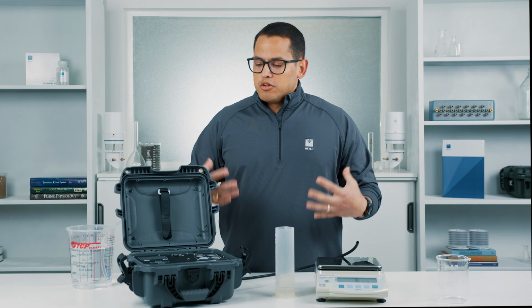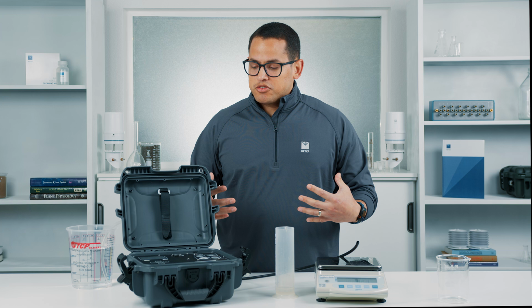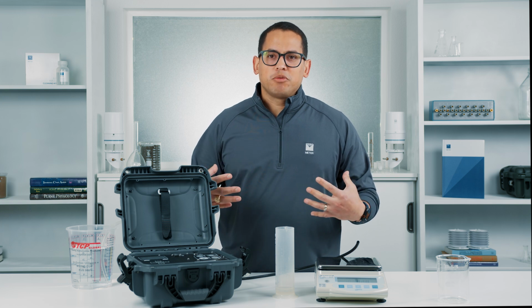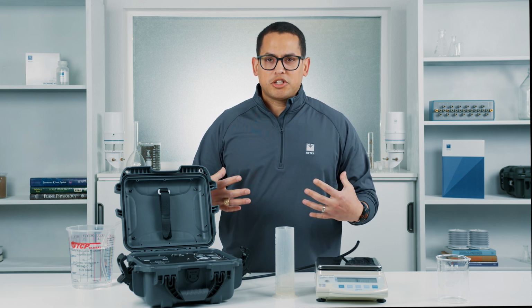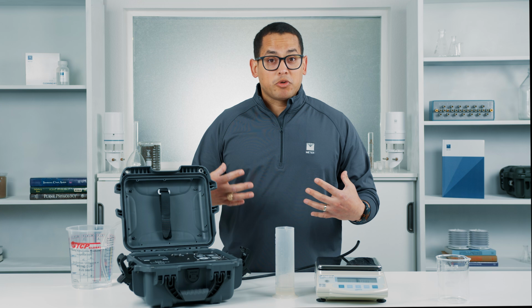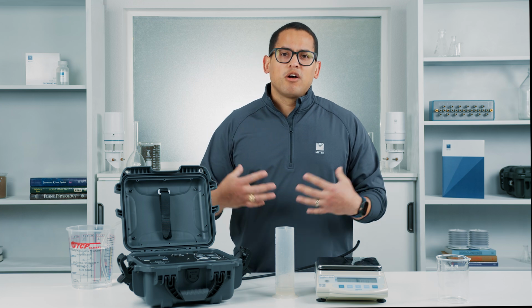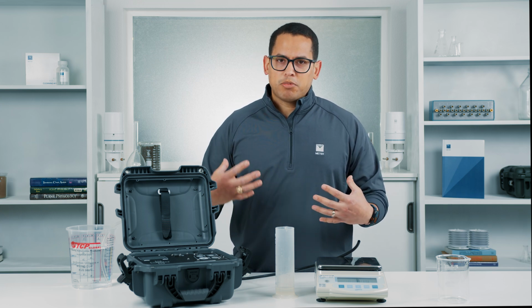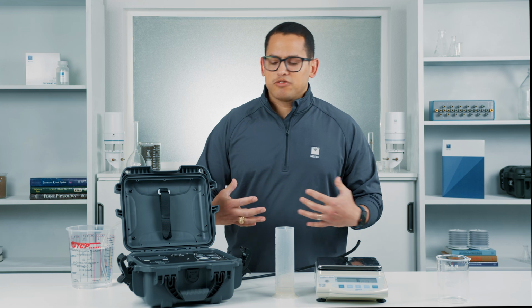Okay. So you'll see here that now in the screen, we have the option to enter the volume of water that was pumped out of the SATURO. So now that we have that measurement, we're going to go ahead and put in 30 milliliters for the volume of water that was pumped out. And that's going to set our new calibration for the SATURO.